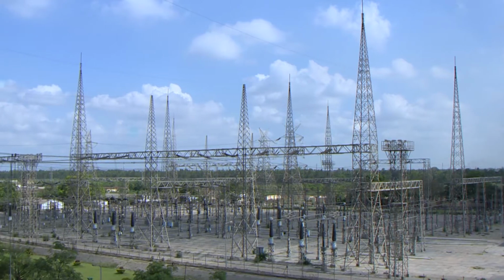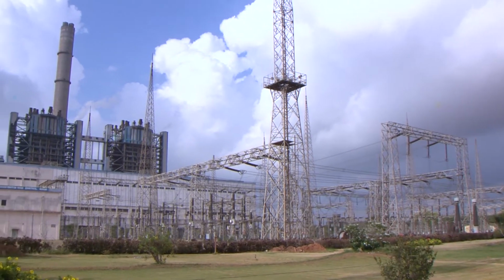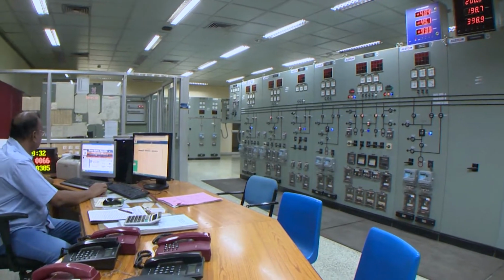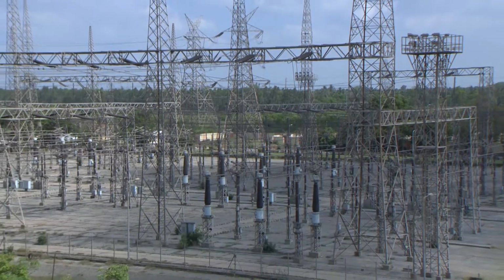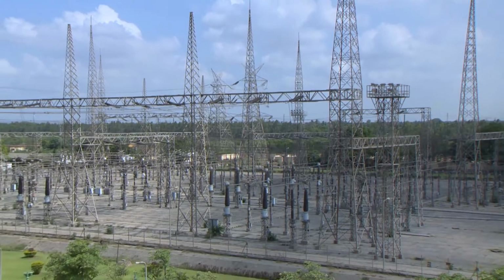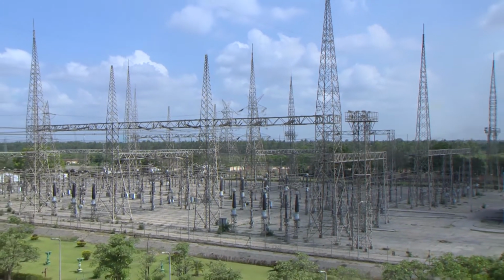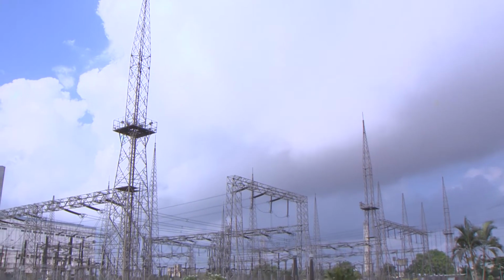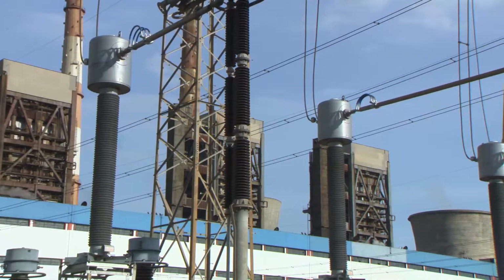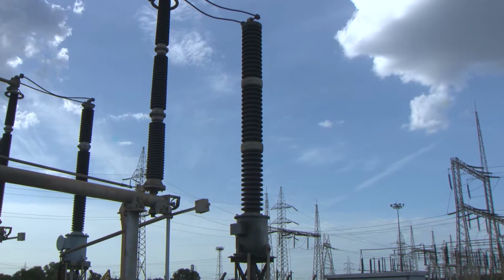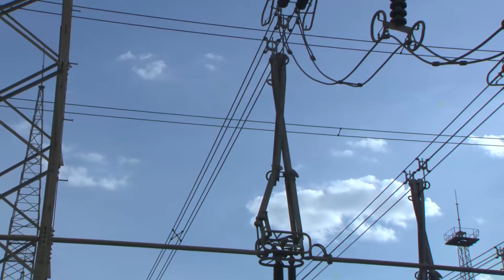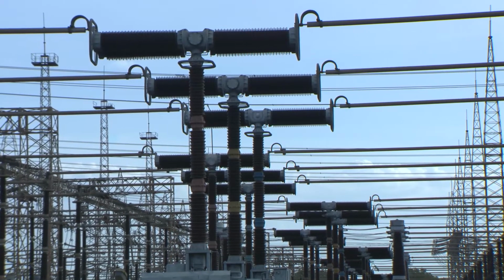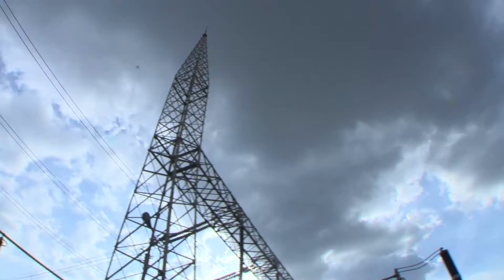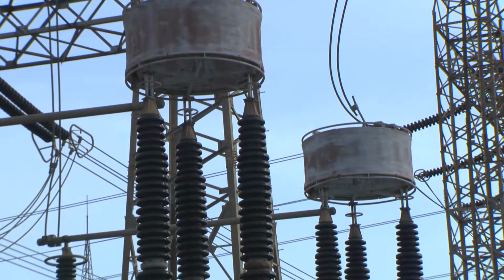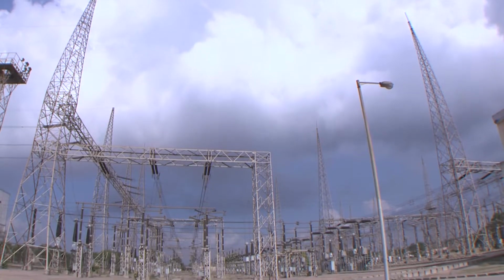Switch yard. The generated power is distributed through switch yard and is regulated from switch yard control room. In switch yard, there are main buses which are common point, connecting number of incomers and feeders. Apart from main buses, there are transfer bus, bus coupler, current transformer, capacitor voltage transformer, isolator, extra high voltage circuit breakers, earth switches, lightning arresters and wave traps that are located in switch yard.